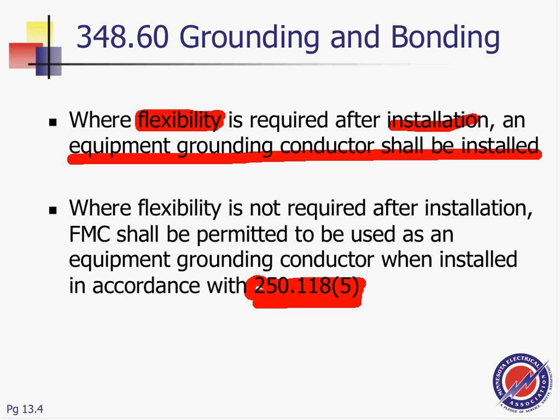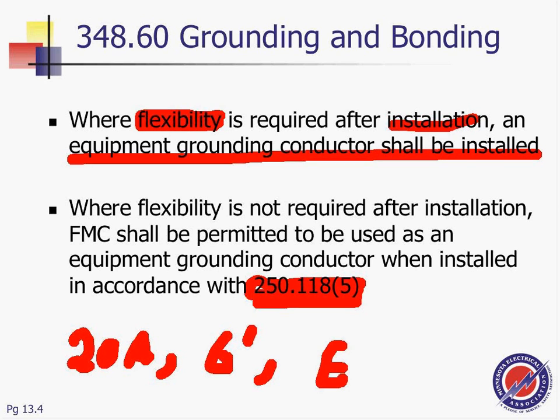Long story short, to use it as an equipment grounding conductor, guys: number 1, you need 20 amps, and number 2, 6 feet or less. An equipment grounding conductor is needed if it's flexible, like for machines. If it's for fixtures, you don't need it. For fixtures, where flexibility is necessary after installation, an equipment grounding conductor shall be installed. So if flexibility is needed, then you can't use it. So that's basically it, with fittings that are listed. So really it's 20 amps or less, which applies to all lighting fixtures. If you guys are using lighting fixtures, that's exactly what we do.